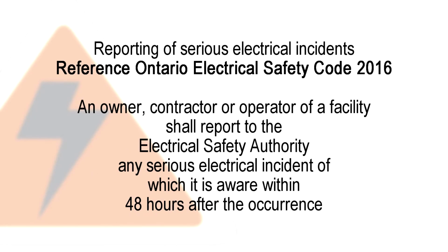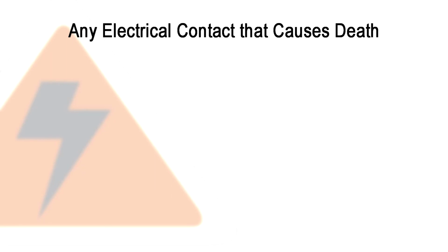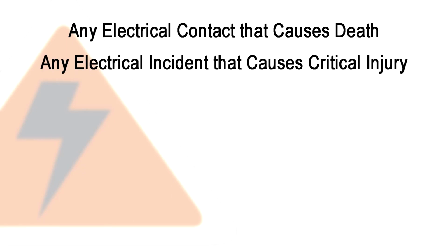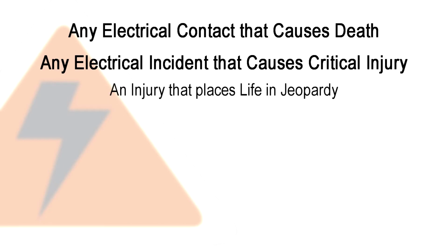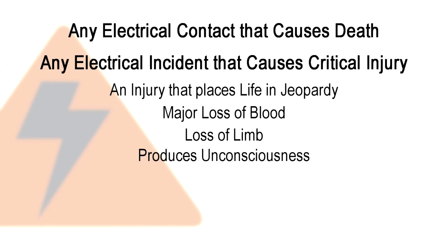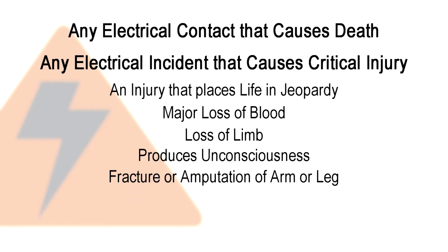For example, in the province of Ontario, under the Ontario Electrical Safety Code 2016 edition, an owner, contractor, or operator of a facility shall report to the Electrical Safety Authority any serious electrical incident of which it is aware within 48 hours of occurrence: any electrical contact that causes death, or any electrical incident that causes critical injury, such as an injury that places life in jeopardy, major loss of blood, loss of limb, produces unconsciousness, fracture or amputation of arm or leg (but not fingers or toes), burns to a major part of the body, or loss of an eye.